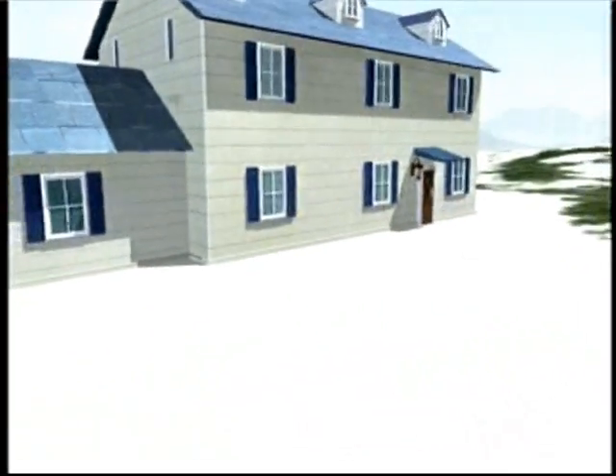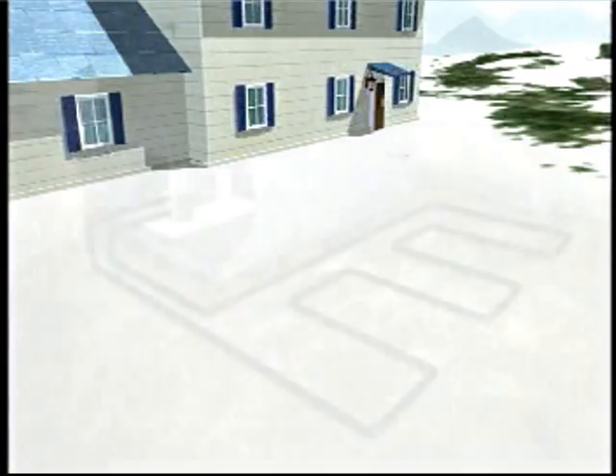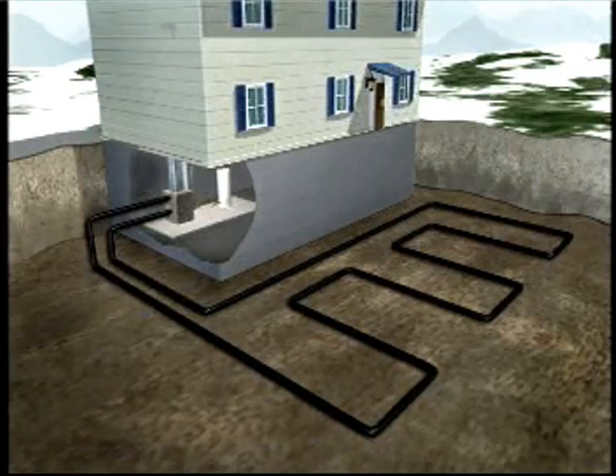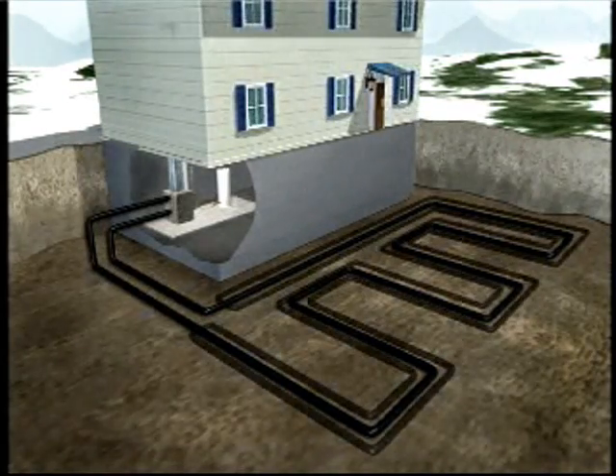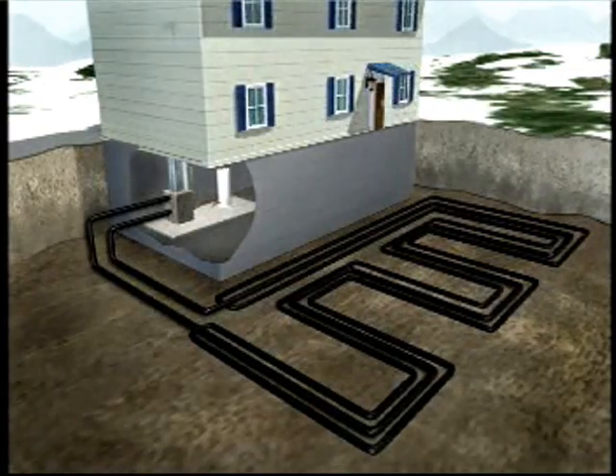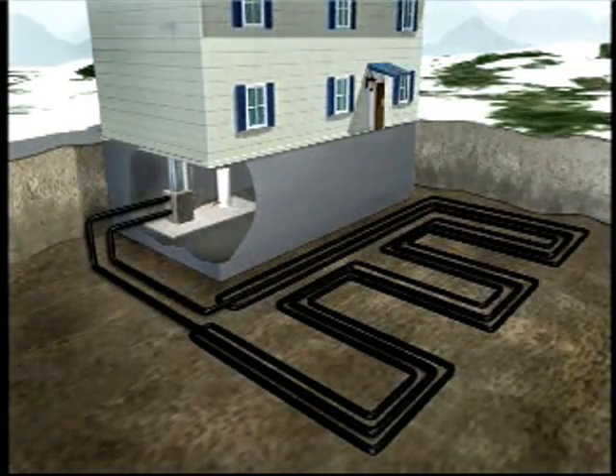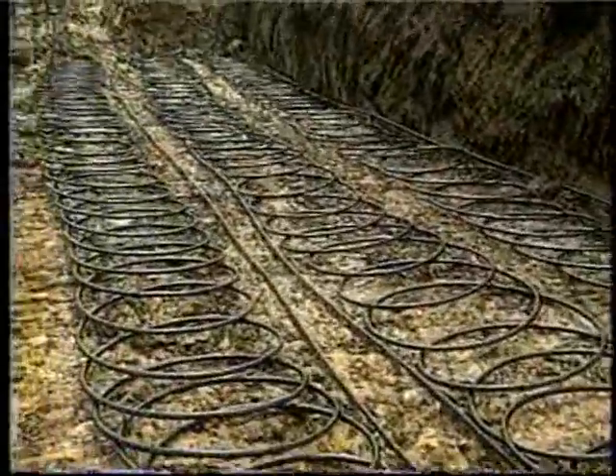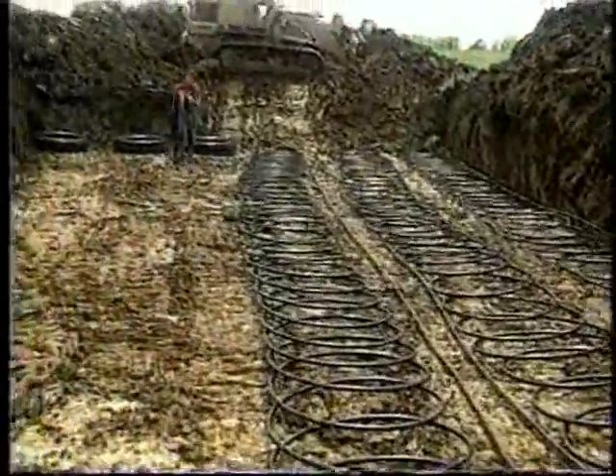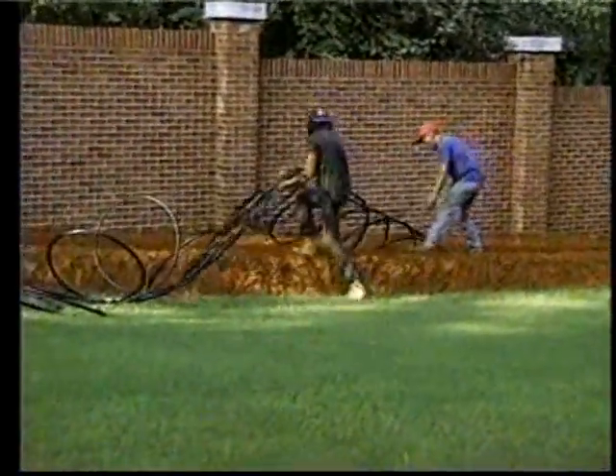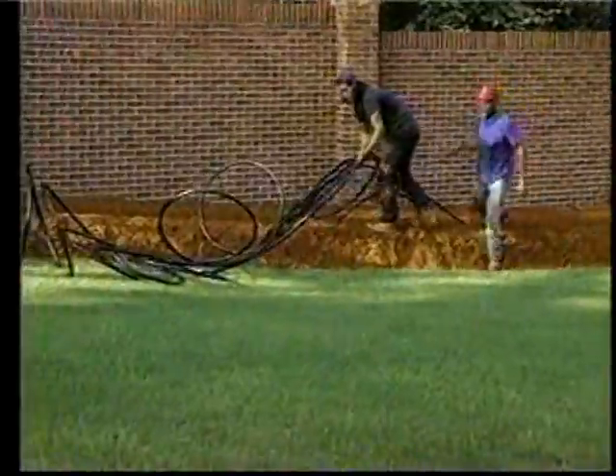In some installations, the pipes of a closed-loop system can be placed in a horizontal trench dug below the frost line. The number of pipes in each trench and the number of trenches needed will vary depending on the size of the geo-exchange system being installed and the type of soil found in the area. To minimize trenching, slinky coils — spring-like coils of polyethylene pipe — can often be used to increase the pipe surface area and thus the heat exchange per foot of trench.